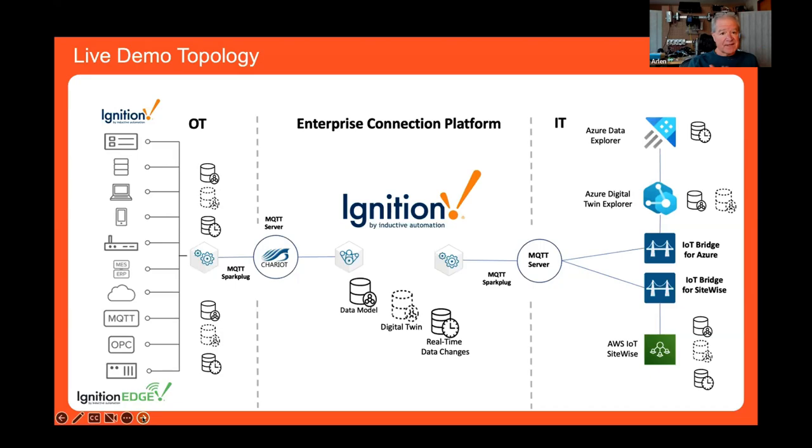One of my favorite things is enumerations. We're all awash in enumerations, where we have PLCs and RTUs and flow computers and factory automation equipment, and it's publishing an integer value. Or no, we're polling for an integer value, and it comes back 0, 1, 2, 3. Well, the plant engineer knows what that means. Maybe it's a motor operated valve. If limit switch open on open is this and limit switch close on open, then that means it's gone from closed to in transit and then to open. But on another motor operated valve, that might be completely different.